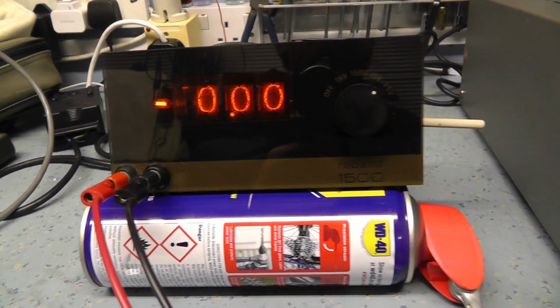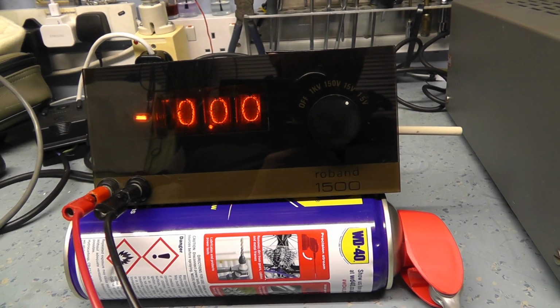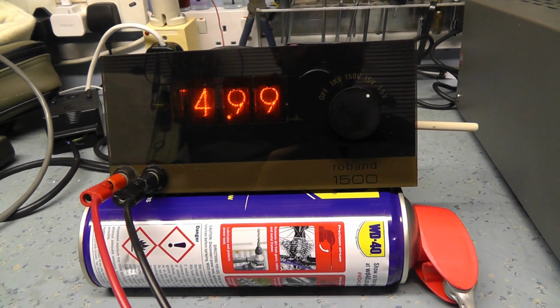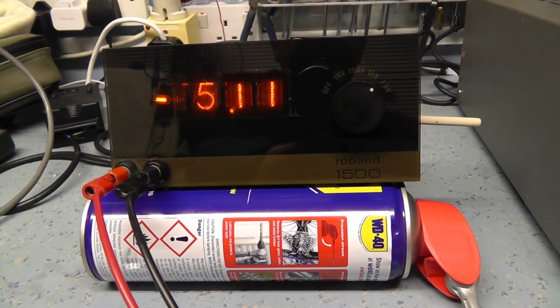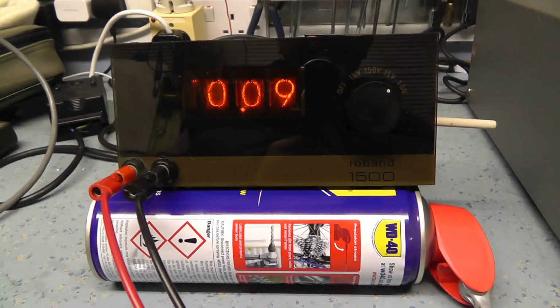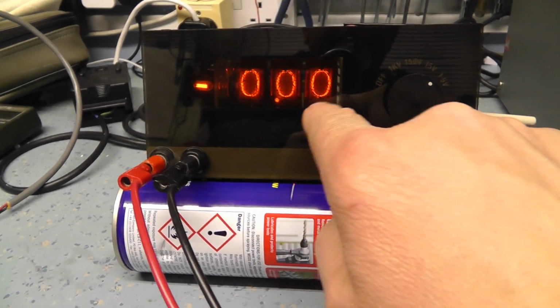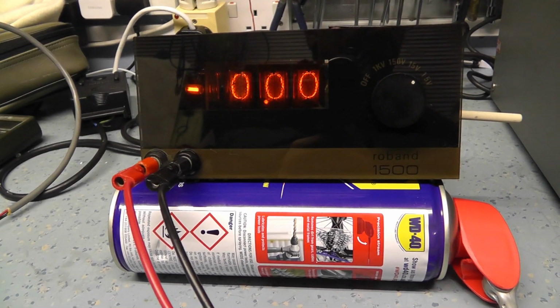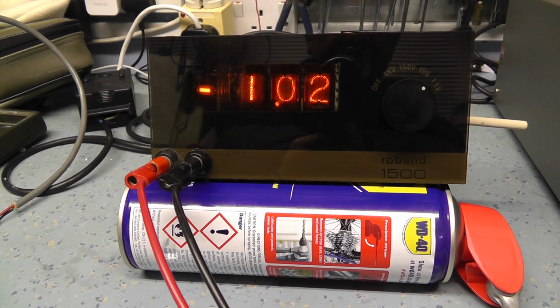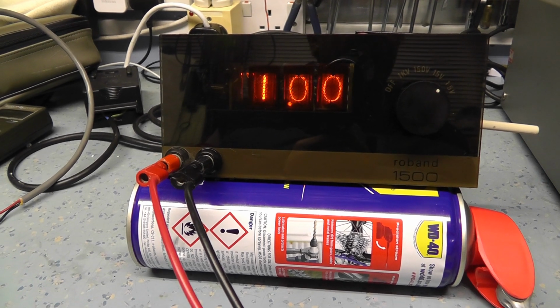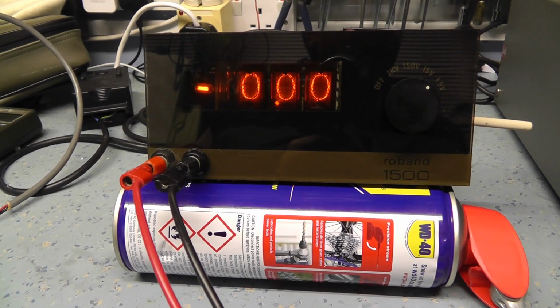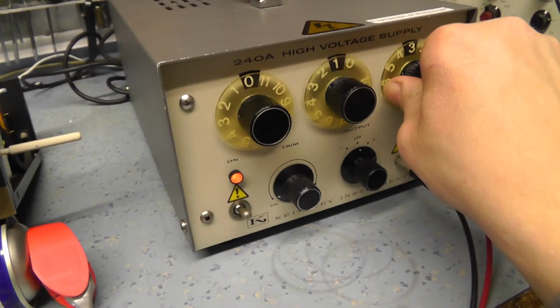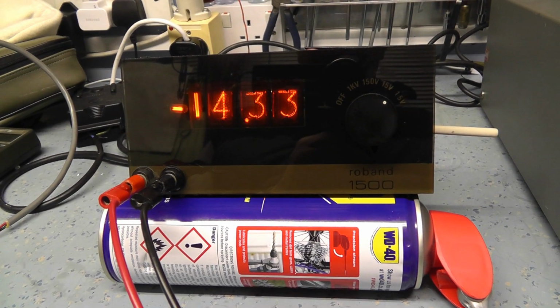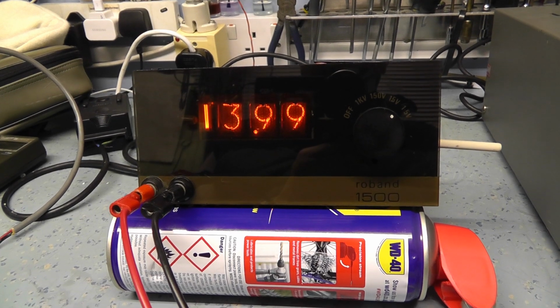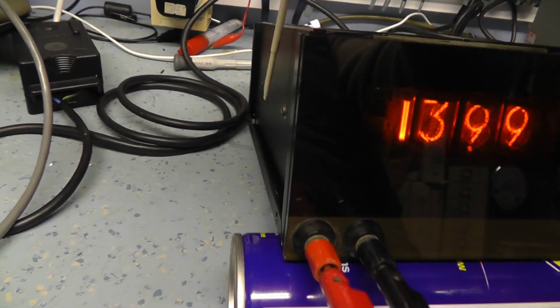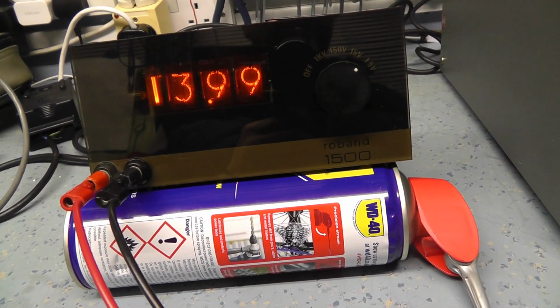Let me just try the lower ranges and see what that does. So this is 5 volts. Reverse 5 volts. Yeah. So we've got an imbalance here. Initially I thought the imbalance would show up as a negative figure here, but it doesn't. It only affects it if you actually put a voltage into it. So minus 1 volt, plus 1 volt. So clearly we've got an offset there. Bear in mind I'm doing this by eye. I'm going to go to 14 volts and adjust the 14 volt setting there, 14.33, 13.99. So I'm going to take this cover off again, have a twiddle around in here so we can get that balance correct, and then we'll have another go.